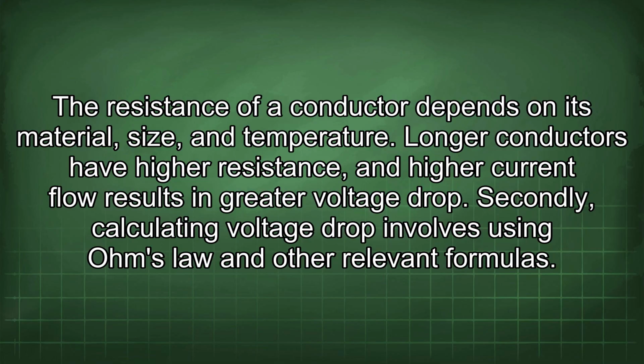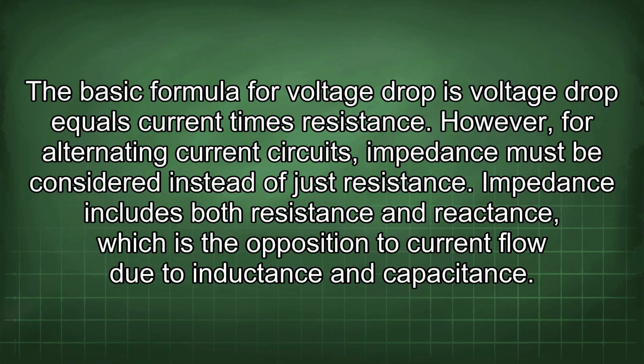Secondly, calculating voltage drop involves using Ohm's law and other relevant formulas. The basic formula for voltage drop is voltage drop equals current times resistance. However, for alternating current circuits, impedance must be considered instead of just resistance. Impedance includes both resistance and reactance, which is the opposition to current flow due to inductance and capacitance.